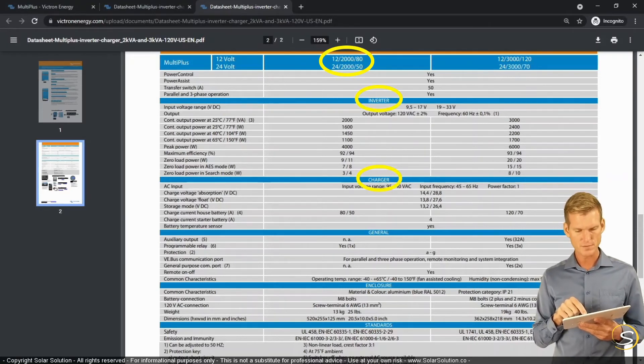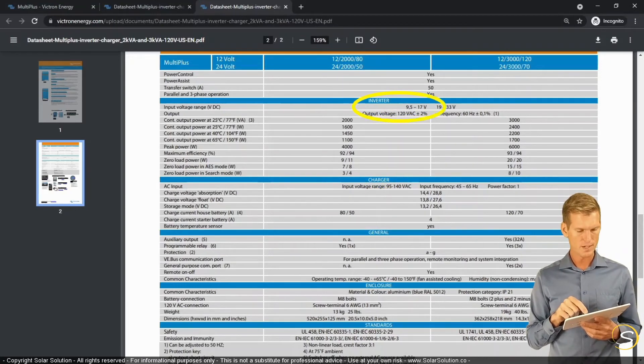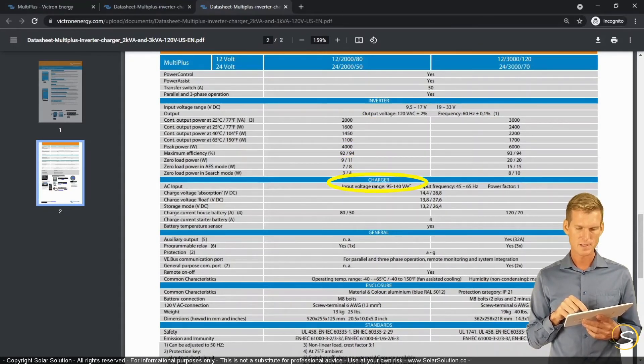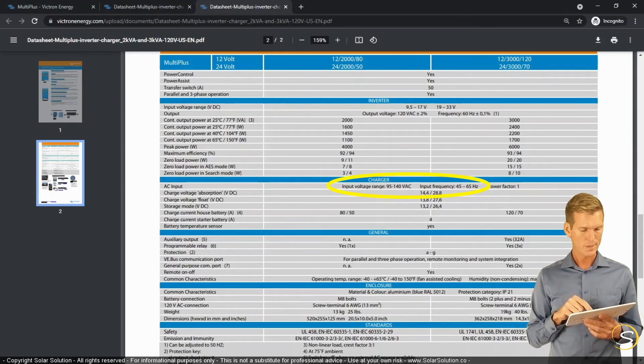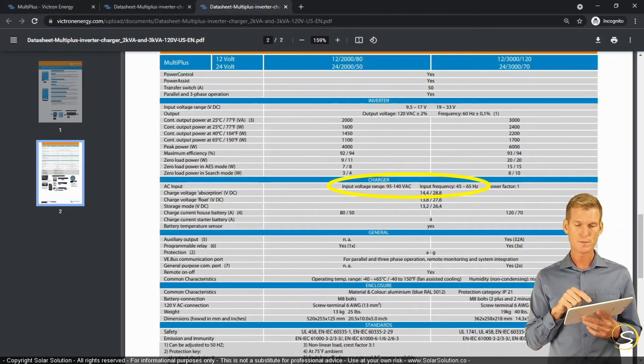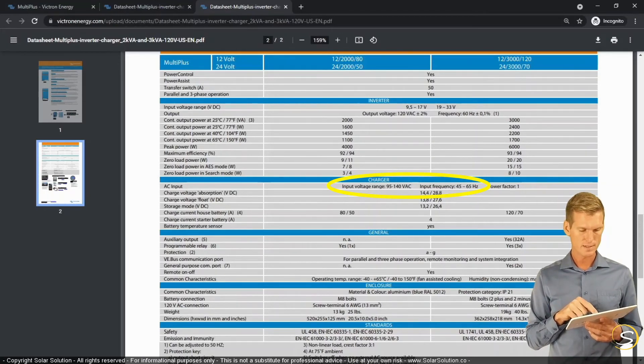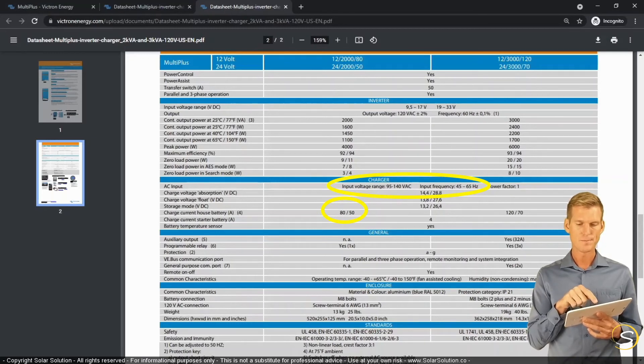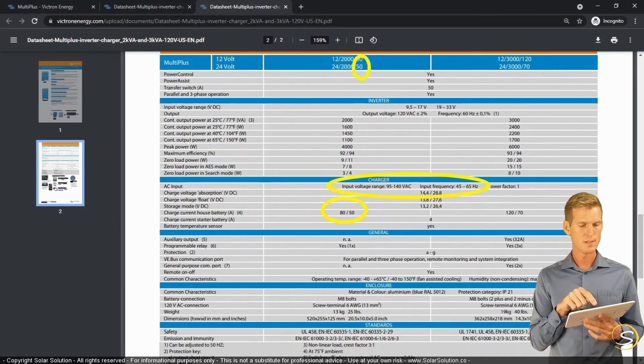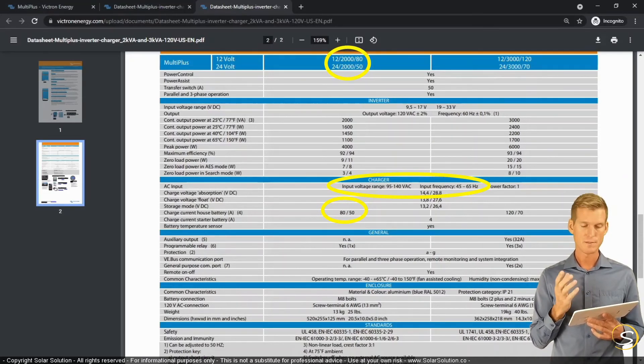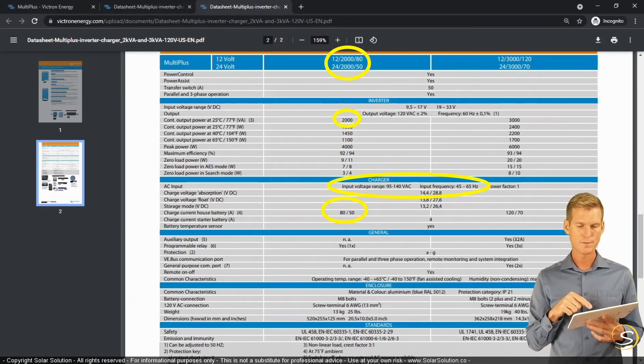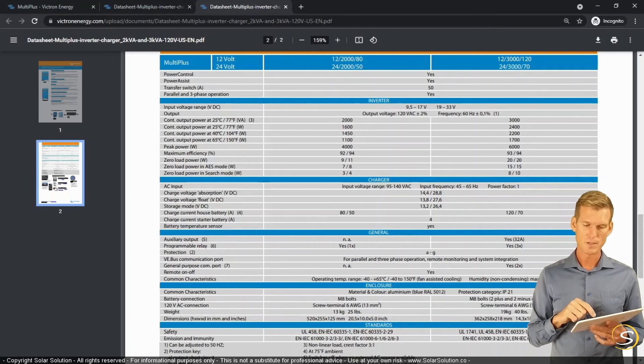The inverter section shows input voltage range, continuous output (the nominal output), and a peak power output of 4000 W. The charger section has a wide AC input range for both frequency and voltage. Depending on whether it's a 12 or 24-volt system, it can charge at 80 or 50 amps respectively. The model code makes this clear: the first value is the battery bank voltage, the second is continuous output power at 25°C (77°F), and the last value is the maximum charge current in amps for the battery bank.